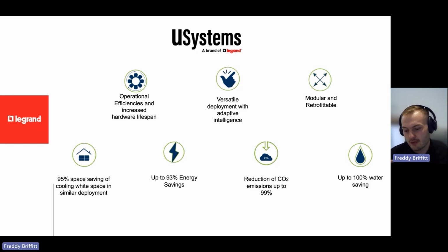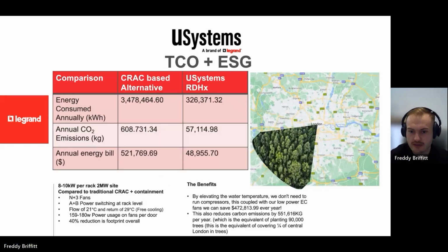As I said, we have a significant reduction in CO2 because we're not necessarily running a chiller or a compressor on the plant on the outside that services the rear doors. We can do it with free cooling. And we see a significant, up to 100%, water saving because we can operate a closed loop system where we're just pumping the water back around the system. Now, how does this help you?